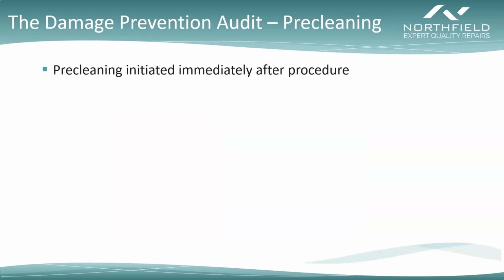Next, we're going to move into the pre-cleaning process. Now, it's very critical that the pre-cleaning process be initiated immediately following the procedure. Some of the bodily fluids that we have to deal with, like mucus, for example, will harden very quickly. And so if pre-cleaning is not done every single time as quickly as possible, that mucus will harden. And when it hardens in certain areas, like the air-water channel, it's very easy for those channels to get clogged. And when they get clogged, there's nothing else you can do for them. They're going to have to go out for repair.